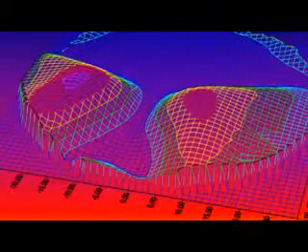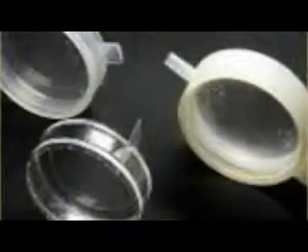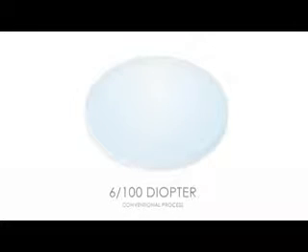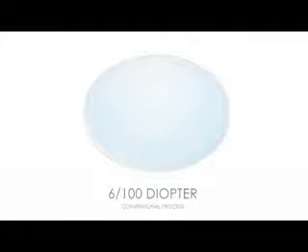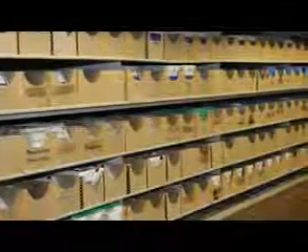Conventionally surfaced progressives, or semi-finished lenses, are the foundation of the PAL market today. The lens manufacturer begins with the lens design, creates a ceramic mold, then a glass mold, and the result is a semi-finished lens blank with up to 6-100ths of a diopter in accuracy. The add power is already on the progressive lens design. Optical laboratories then stock these lens blanks in a set number of base curves, and when ordered, surface only the back side of the lens to create a finished PAL lens.